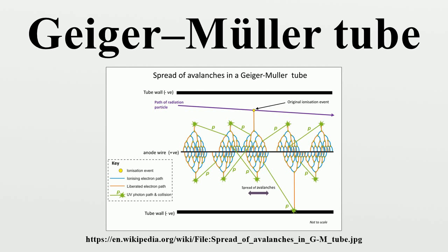Types of tube. Broadly, there are two main types of Geiger tube construction: end-window type for alpha particles, low-energy beta particles, and low-energy X-rays. The usual form is a cylindrical end-window tube. This type has a window at one end covered in a thin material through which low-penetrating radiation can easily pass. Mica is a commonly used material due to its low mass per unit area. The other end houses the electrical connection to the anode.